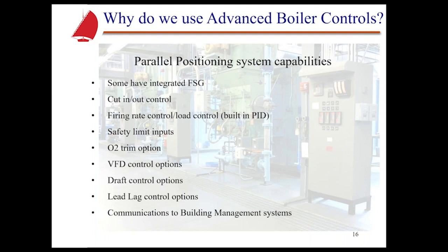Another advantage, or some of the capabilities of the parallel positioning systems these days, is that some have actually integrated flame safeguards. When parallel positioning was first introduced, they worked in conjunction with an external flame safeguard. So the actual flame safeguard turned over control to the parallel positioning system, which was a separate component for modulation and control of the air fuel ratio. But a lot of the systems these days have that flame safeguard built in, and that's a big advantage because then all of the system basically can communicate without having external wiring, and that's important.